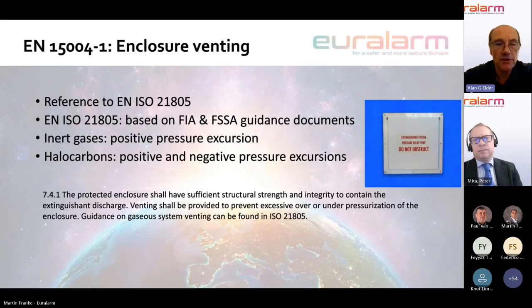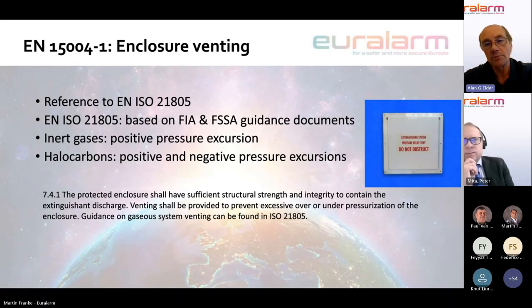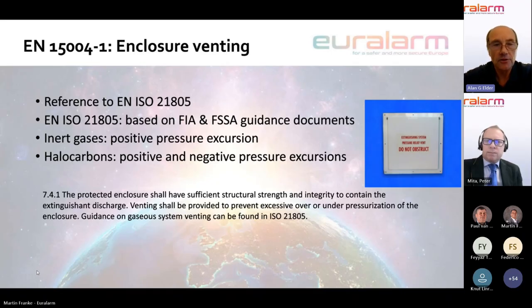In 2023, a new ISO standard was published, which is ISO 21805. It was published as a joint work item with CEN and is published as EN ISO 21805. For the first time in the EN 15004 standard, a requirement to take notice of EN ISO 21805 is there, and you will see again the clause: the protected enclosure shall have sufficient structural strength and integrity to contain the extinguishing discharge. Venting shall be provided to prevent excessive over or under pressurization of the enclosure. Guidance on gas system venting can be found in ISO 21805. So again, giving strength to the arguments to include the appropriate levels of pressure venting within a protected environment.